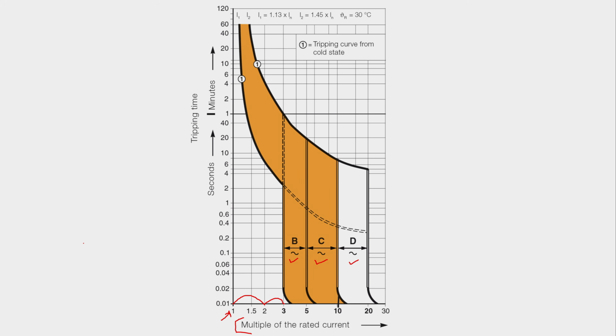So let's say, for example, I wanted to protect for a current of 80 amps. And if I chose a circuit breaker that is rated at 80 amps, notice that it would actually never trip. So if this is 80 amps, because this is the rated current of the circuit breaker and 80 amps is now flowing, it is an overload on that inverter. Notice that the curve never goes past this axis here. So it'll actually never trip.